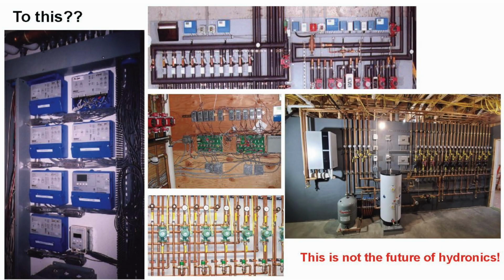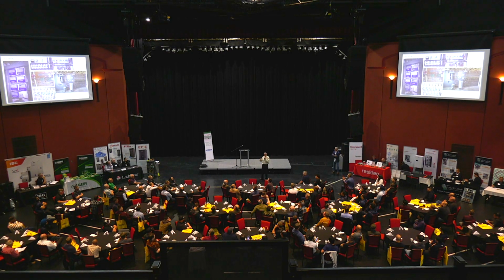So, you've got to think about the word that gets a lot of play these days. It's called resiliency. How many of you read that in articles lately or heard that? And it's a good concept. It's simply the idea that we should design systems so that they can persevere through maybe a 2-day power outage without freezing up, okay? That they don't necessarily fail when the slightest small component might fail. You could have a system, any of these systems, where something as simple as a thermistor could fail or drift out of calibration, and it brings the entire system to a halt. That's really not resiliency.